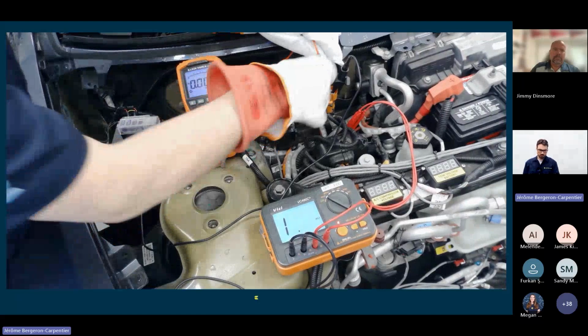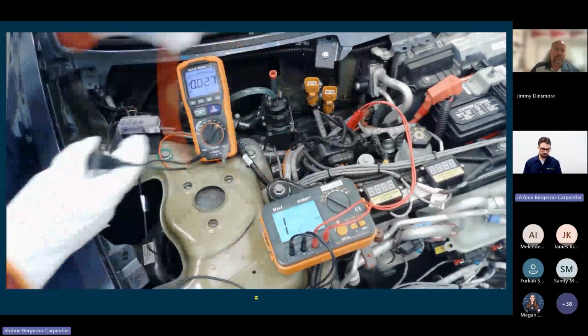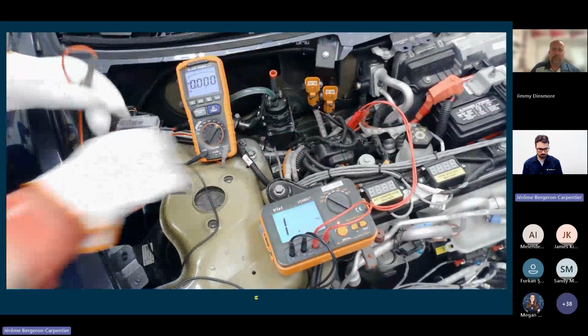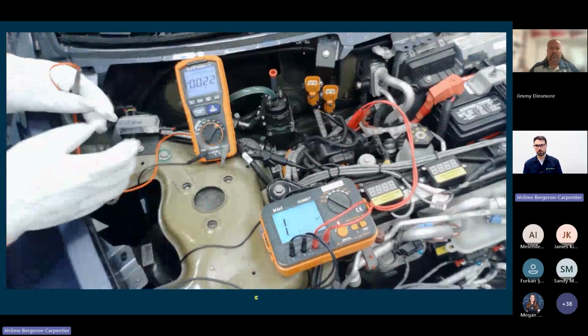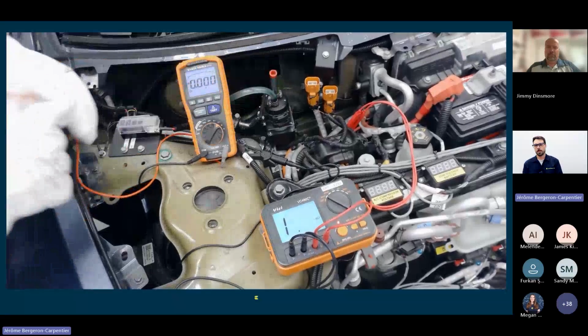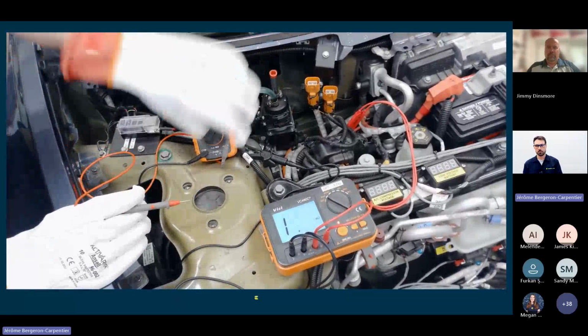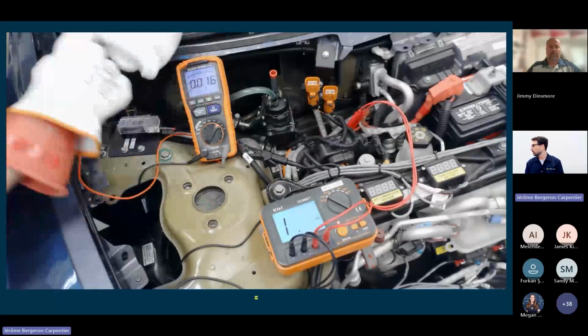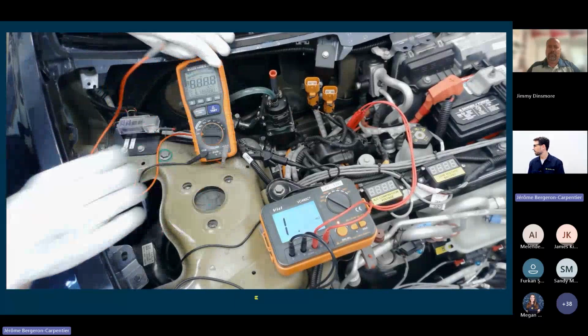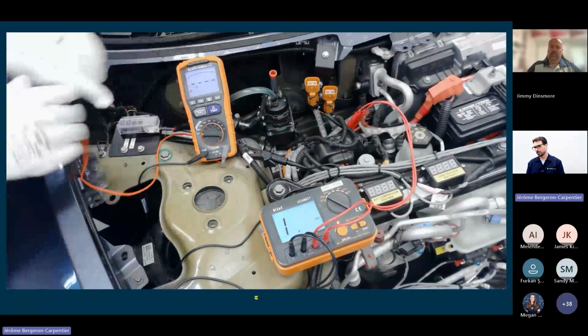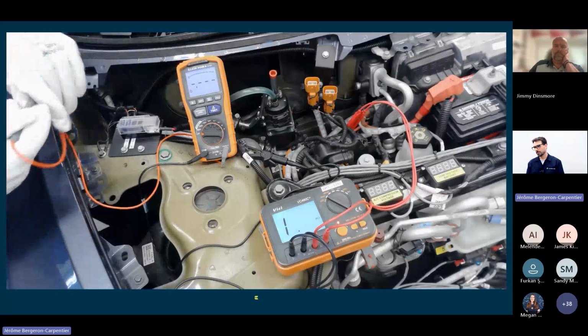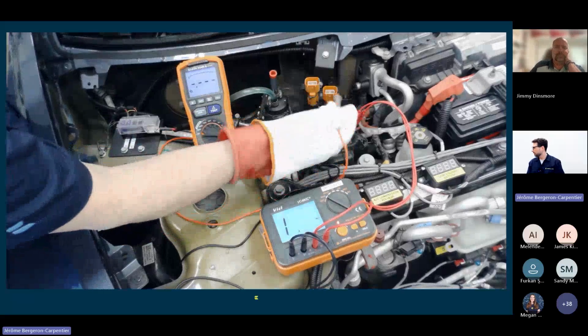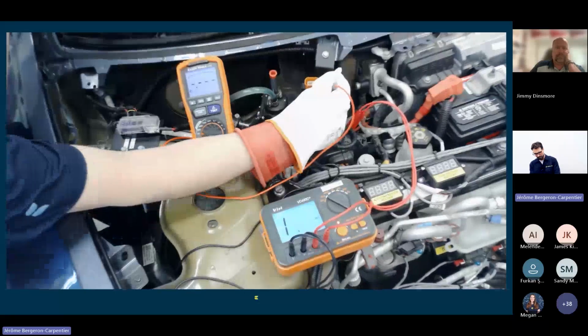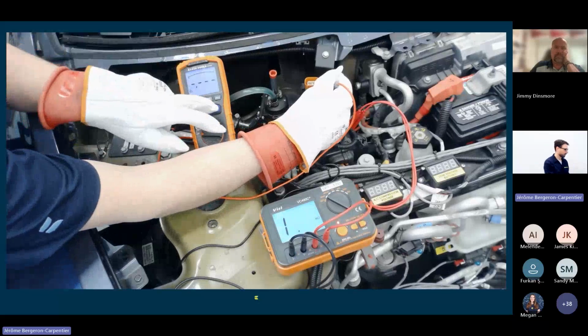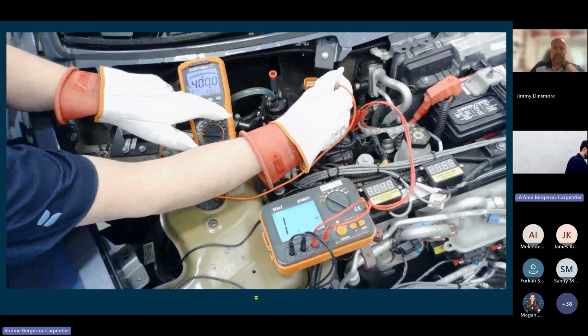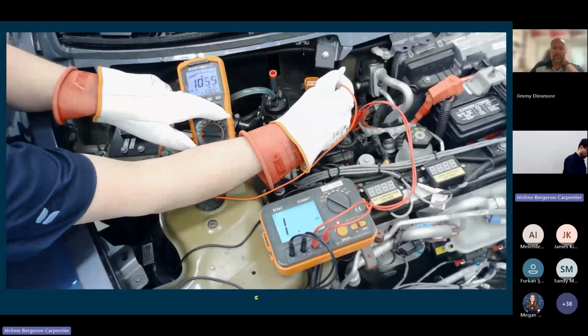So what I'm going to do now is an isolation test, hence the fault that we've shown on our trainer there. I'm just going to do it to chassis, because I could do it at the case of the compressor or so on, but I just want to show what happens. So I'm going to set this to kilovolts. As we do this, I'm on the kilovolt reading for the testing. I'm going to put the probe into the connector and push test.